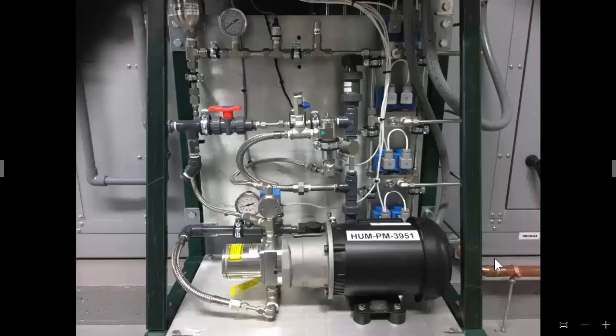So what is really going to happen if something goes wrong? Well, they are energized together. As you can see, there's a power line that comes in here, 24 volts AC, and then it jumpers over to the other coil. So both coils are powered on at the same time, and both coils are powered off at the same time. One is a normally open valve and one is a normally closed valve. The normally open valve is the dump side, the side that lets high pressure escape to drain. The other one is the actual zone valve itself, which lets water from the incoming side through the valve, through this line here, out to the nozzles themselves. So that's the normally closed.